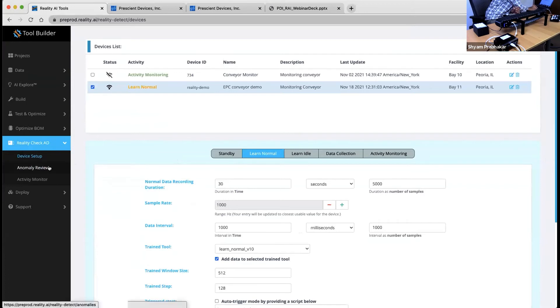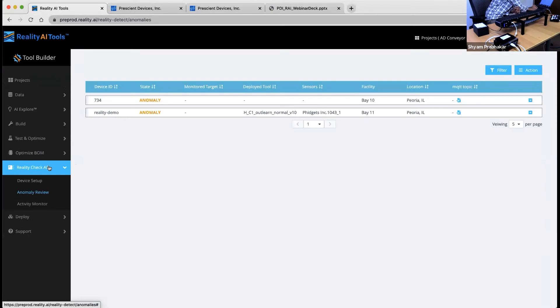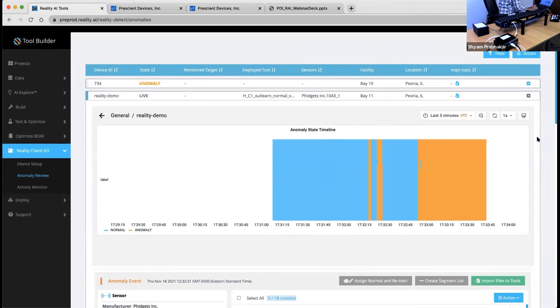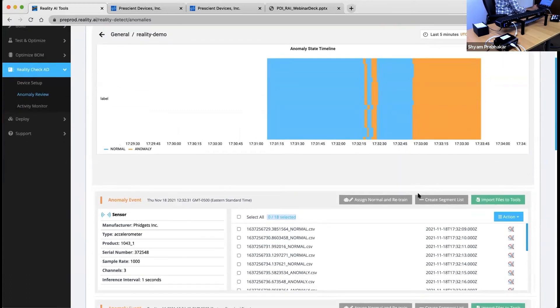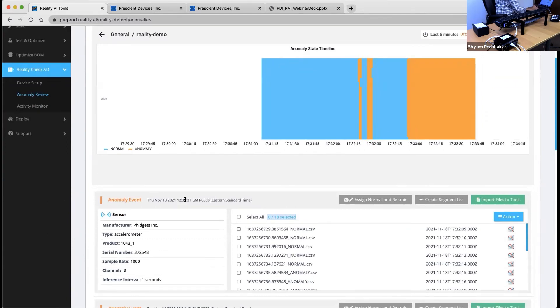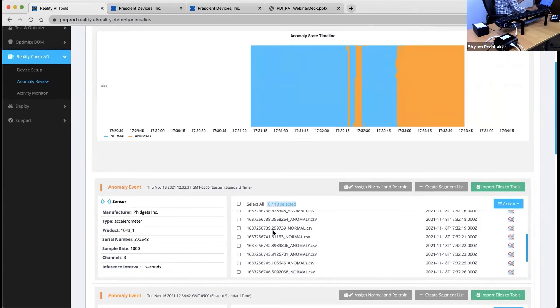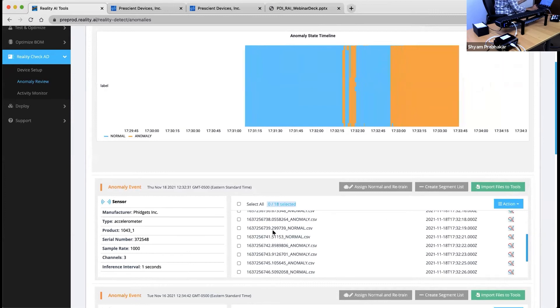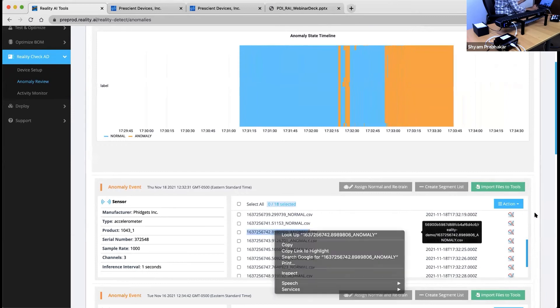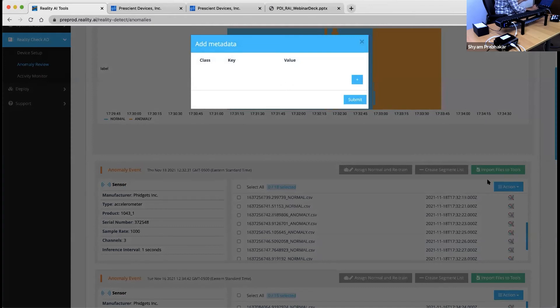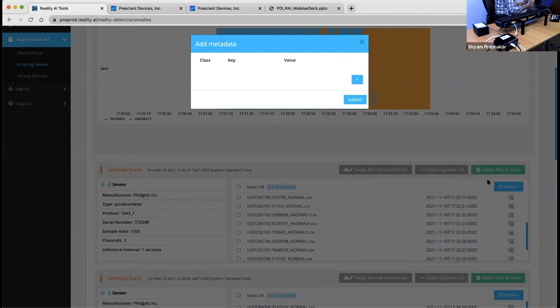It's fairly easy to correct that. This is the last step. We saw how we built the model, we saw how we ran the model, and now I want to show you how we can iterate on the model. We're going to go ahead and relearn or append to our existing model. We're going to add 30 seconds more of data to this model where we're going to train it on idle — the conveyor is off right now — and add to our existing anomaly detection model, teaching it what idle looks like. While that's running, let me take it to the last page on here, which is anomaly reviews. This is where one would come to do that iterative aspect of anomaly detection. In the last few minutes — a couple of minutes ago — we actually detected an anomaly. We actually collect raw sensor data during that brief anomaly period and upload it to S3, so you have all the raw sensor data available for you to analyze.